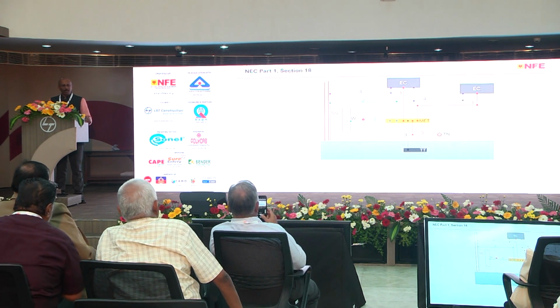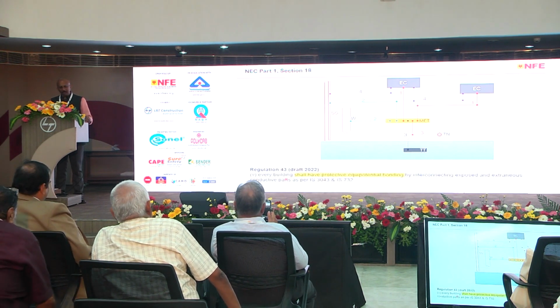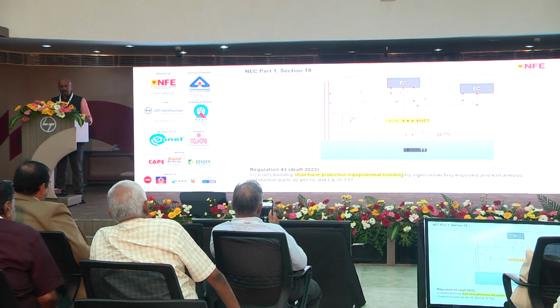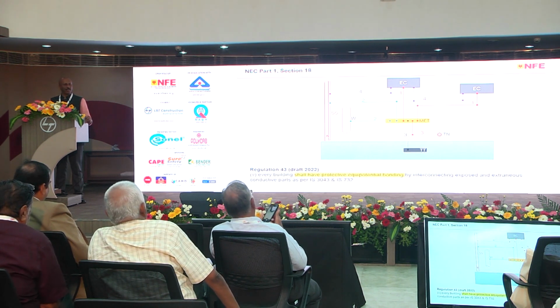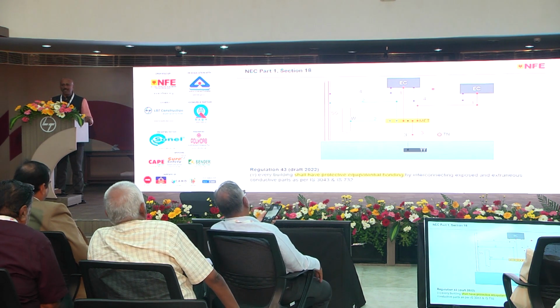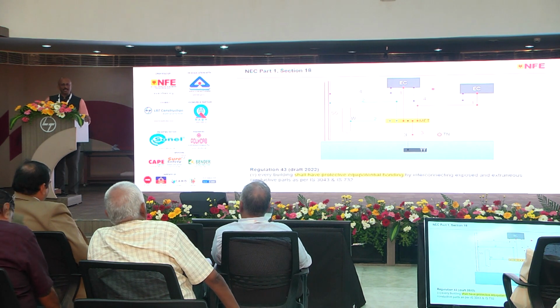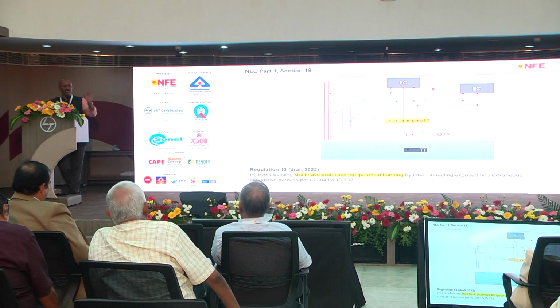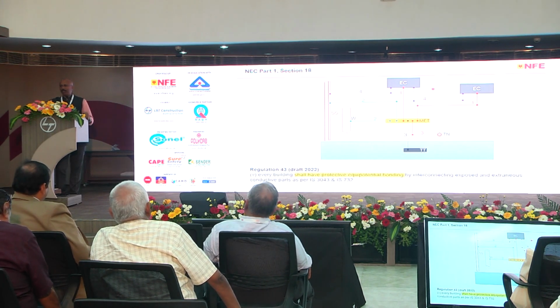Then protective equipotential bonding, regulation number 43, clause number 5 says every building shall have protective equipotential bonding by interconnecting exposed and extraneous conductive parts as per IS 3043, IS 732. And this picture is also there in the NBC. Yesterday I asked a question: out of how many buildings, or what percentage of buildings in Chennai, is this first safety measure implemented? We got an answer, 0%. So this will be a red seal.